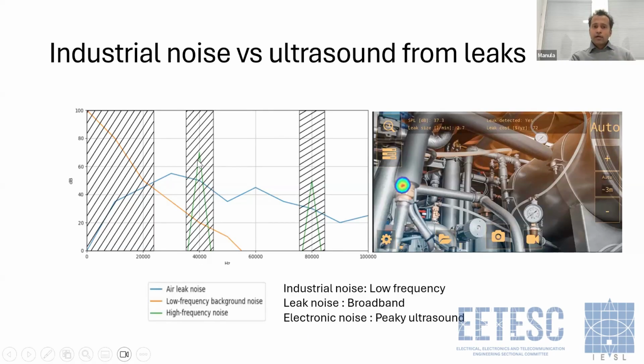There are other types of sound sources, for example electronic noise emitted by sources like switching frequencies. But these cameras have inbuilt filters for them as well, because these sound sources are concentrated in very narrow band frequencies, for example 40 kilohertz or 80 kilohertz, like monotone signals. These peaky signals are also removed by the ultrasound cameras, so they do not affect the detection.